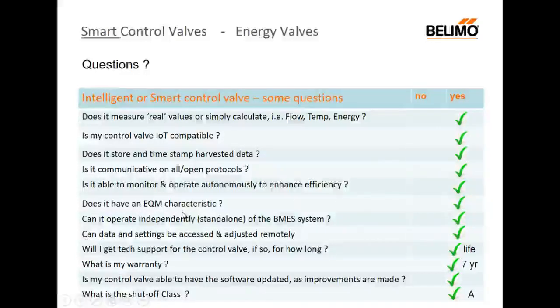It's got to have an EQM characteristic. It's not really a question, it must have it. Can it operate independently? And that is, do I need a building management energy system or will it operate standalone? I know that some BMS systems get turned off after a while because the system encounters problems, the operators don't understand it, so they switch it off. So having a valve that might stand alone and harvest the data on board itself might be interesting.